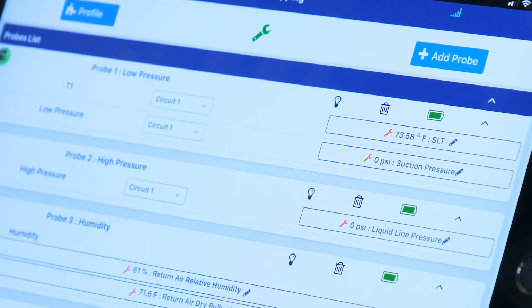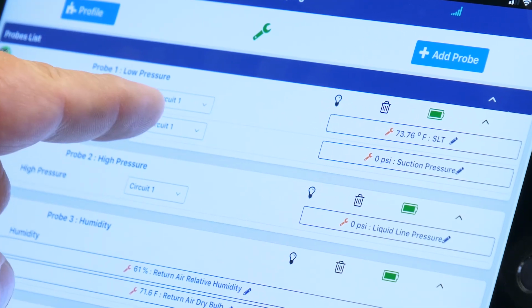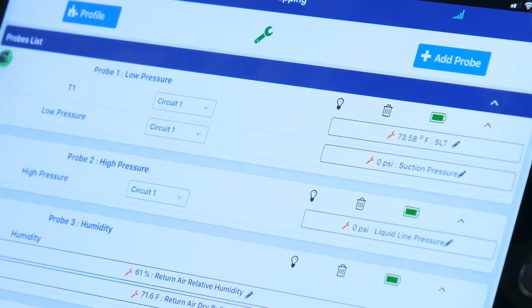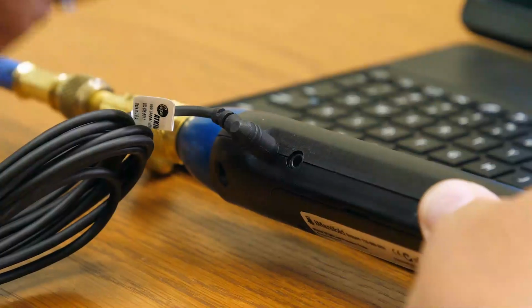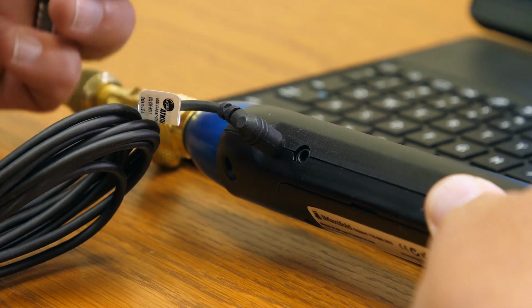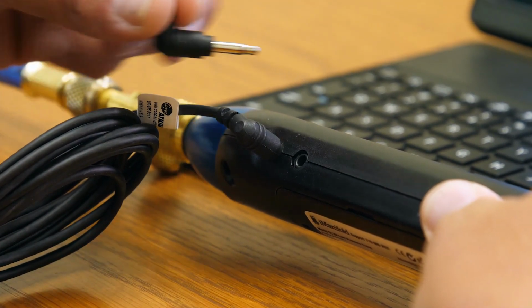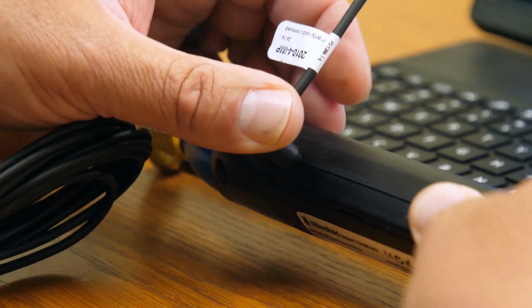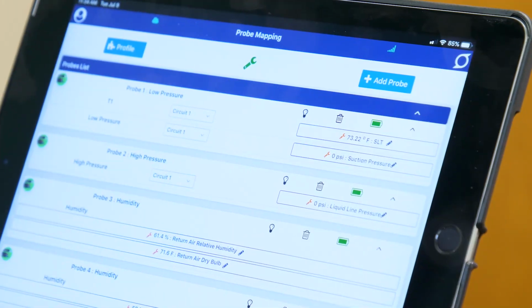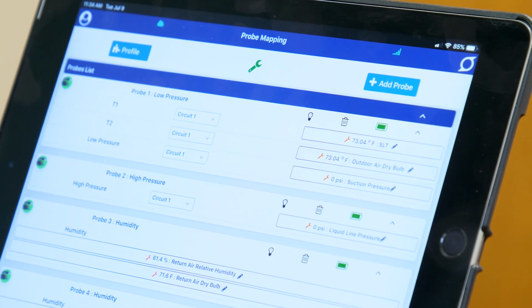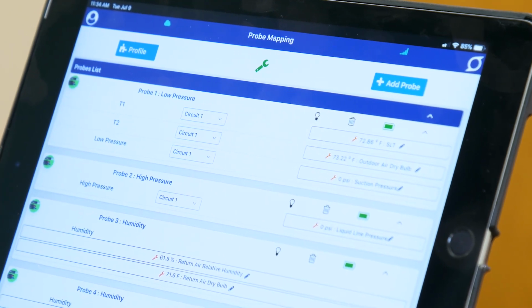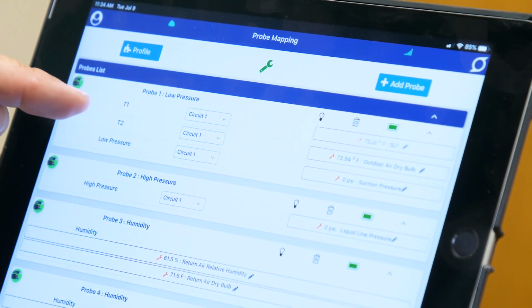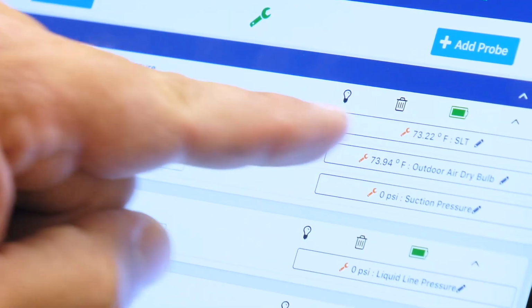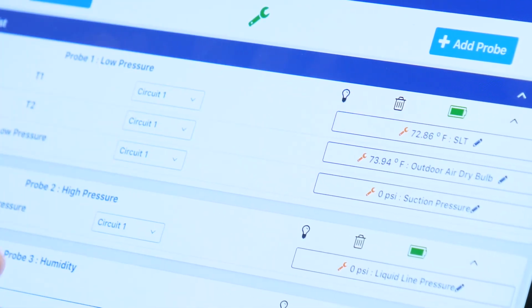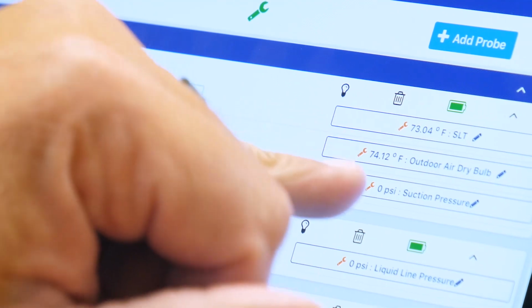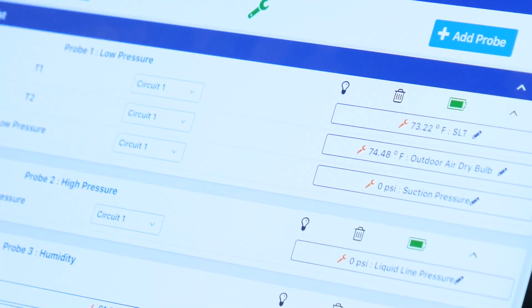So as you can see, when we plugged into T1 circuit 1, it shows our suction line temperature. Now we're going to go ahead and plug in our ambient air temperature thermistor into T2 on the low side probe. Now that both temperatures are plugged in, we're showing a T1 and a T2. T1 shows our SLT, suction line temperature. T2, circuit 1, outdoor air dry bulb.